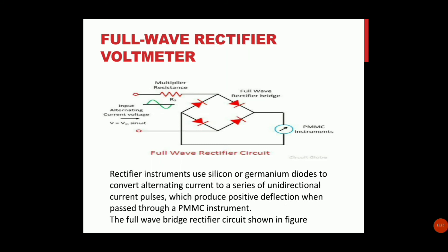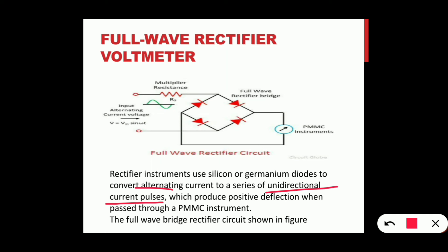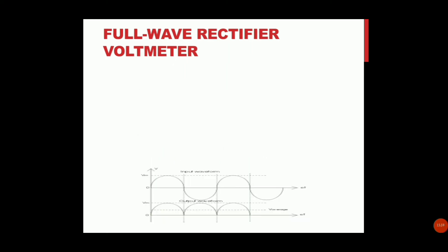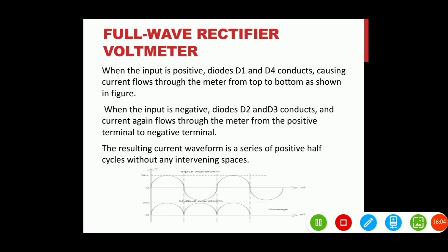Rectifier instruments use silicon or germanium diodes to convert alternating current to unidirectional current pulses. Unidirectional current is DC; alternating current converted to DC produces positive deflection in the PMMC instrument. During the positive input half-cycle, D1 and D4 conduct, causing current to flow through the meter from top to bottom. During the negative half-cycle, D2 and D3 conduct, from positive terminal to negative terminal.